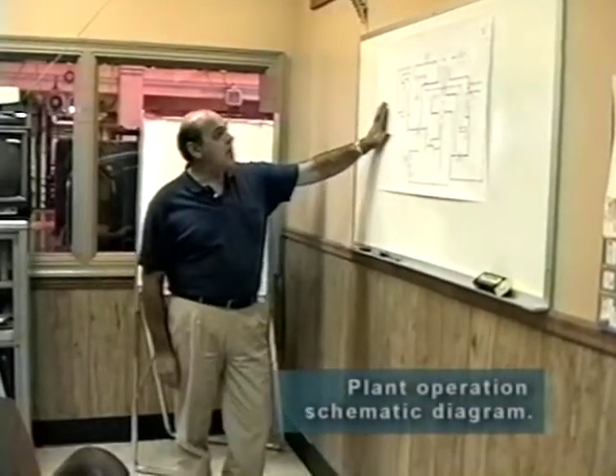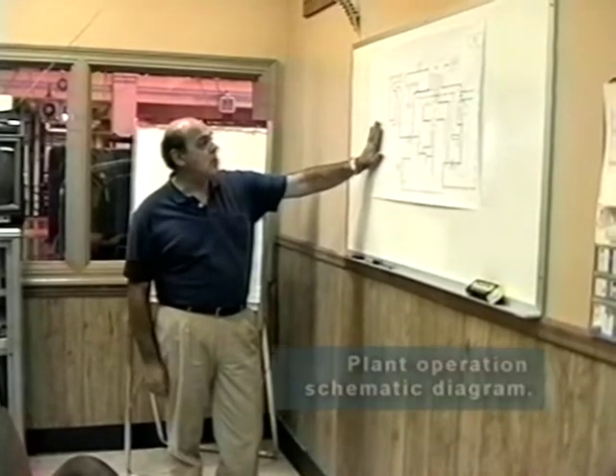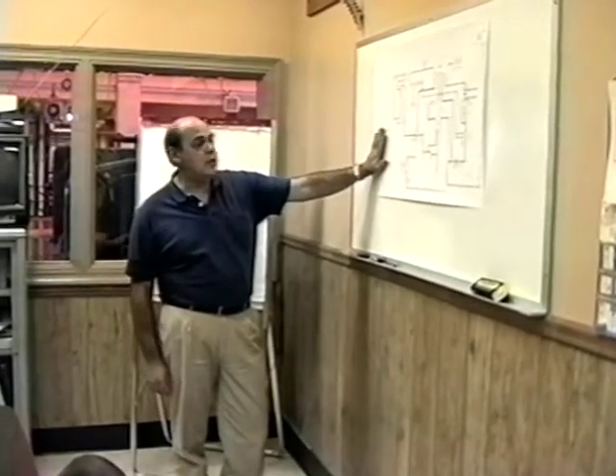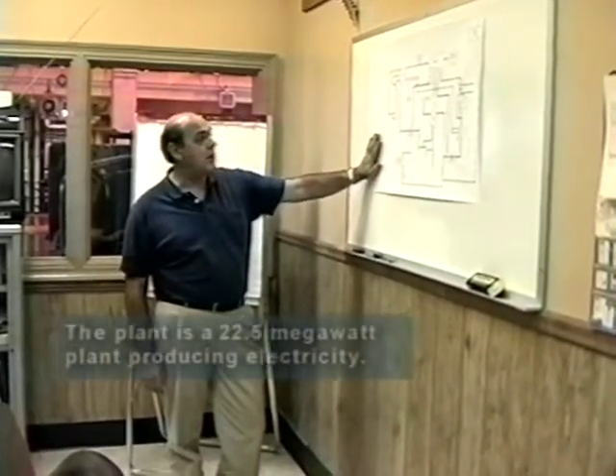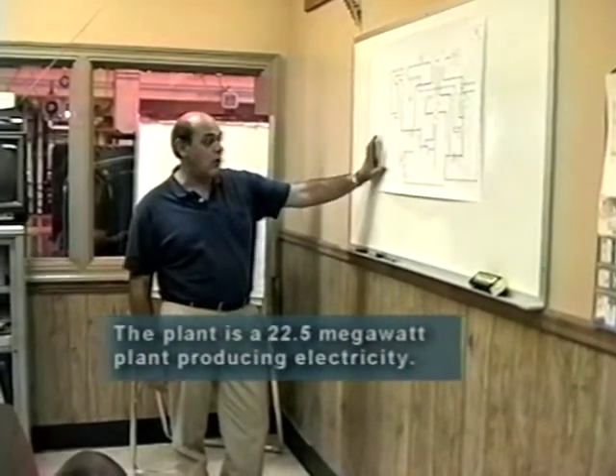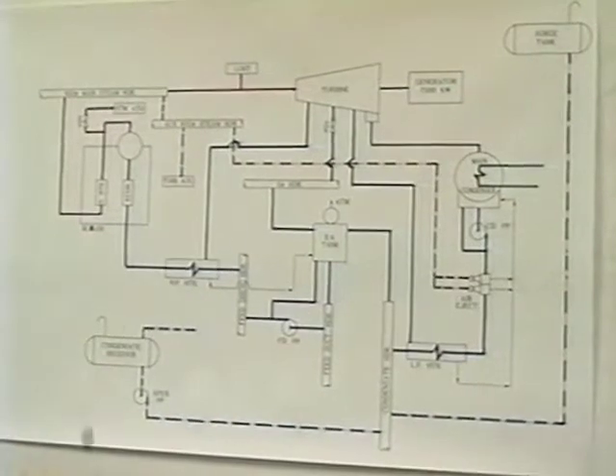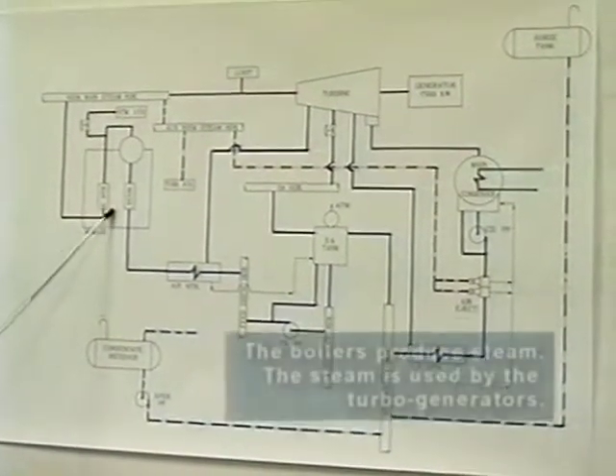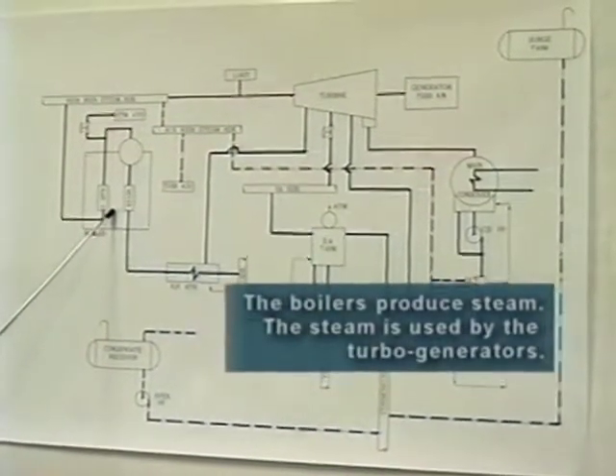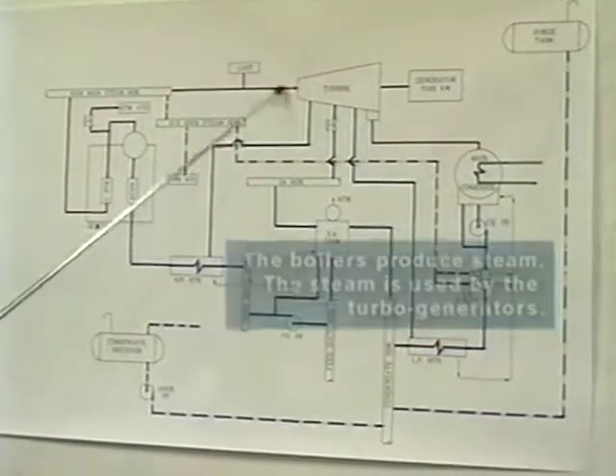This is a schematic of a major cycle at Pierce Station. Pierce Station is a 22.5 megawatt power plant. It's oil fired, number four oil. Number four oil is burned in the boilers right here. Fuel oil is fired in the boilers to produce steam, which in turn is used by the turbo generators.